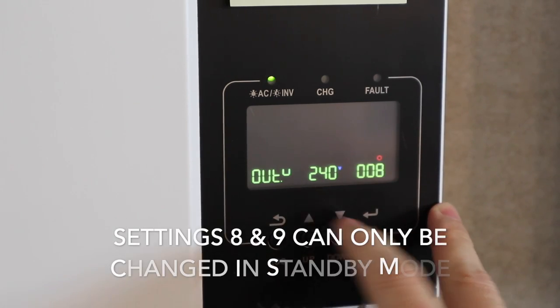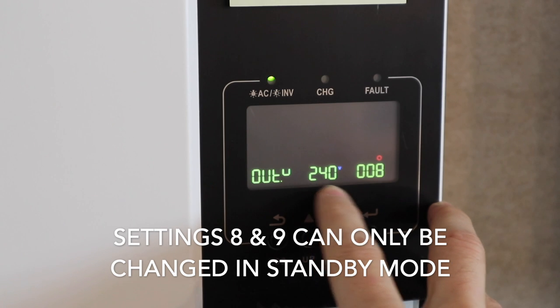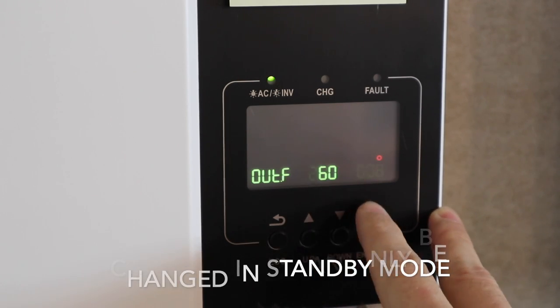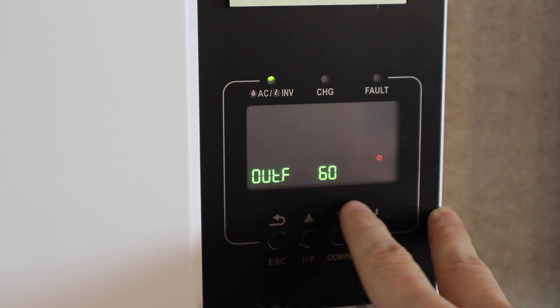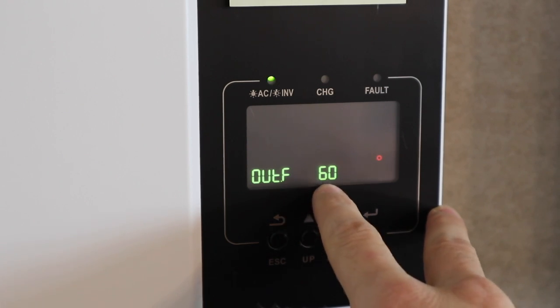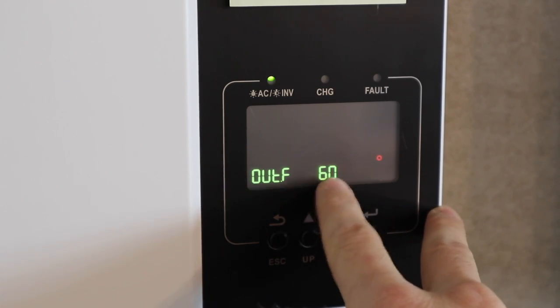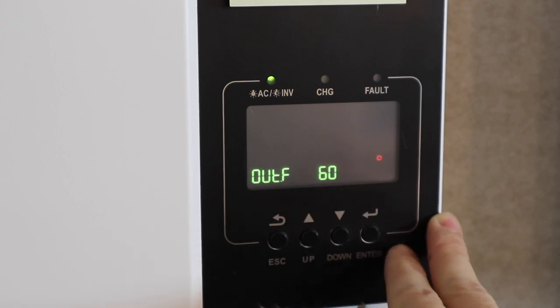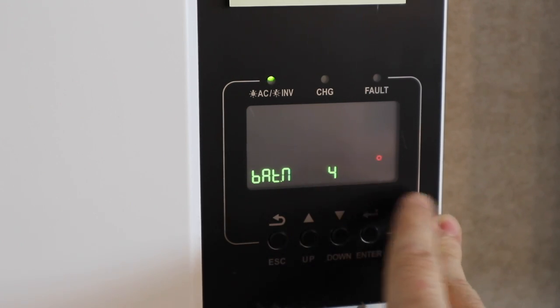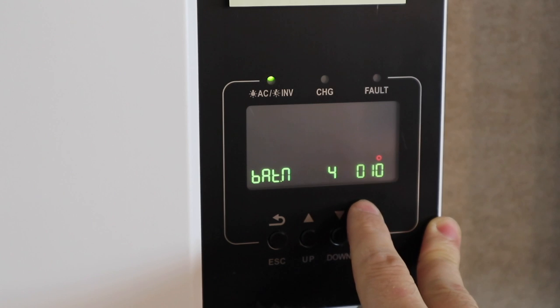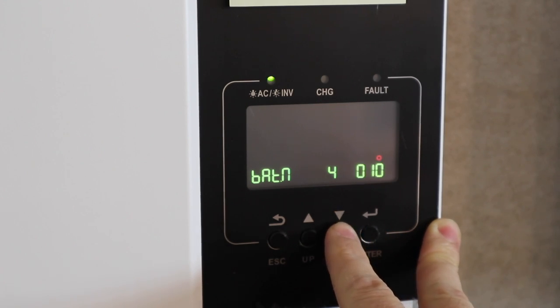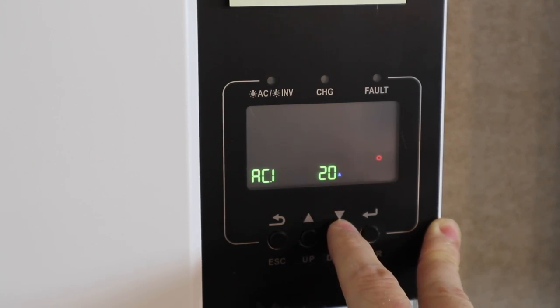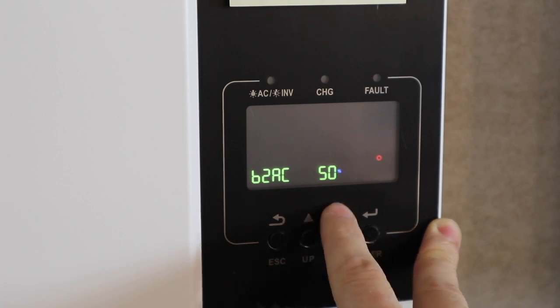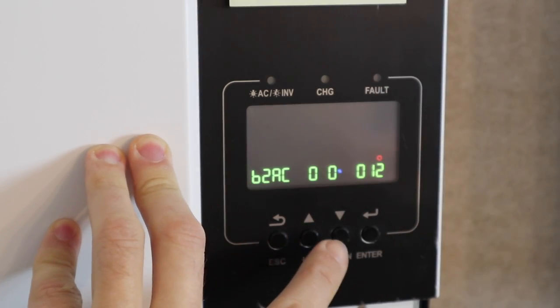So setting 8 for the United States, we need to set it at 240 volt. We're going to scroll to 9 and 60 hertz, because we don't have appliances or anything in our house that works off 50 hertz. So set that to 240 and 60. Setting 10 is only for lead acid batteries. We don't have those. We're going to skip over it. Setting 11 is only for lead acid. Also, skip over that.